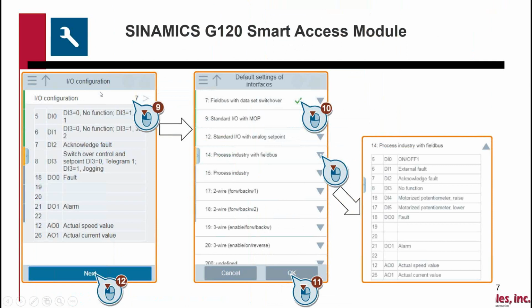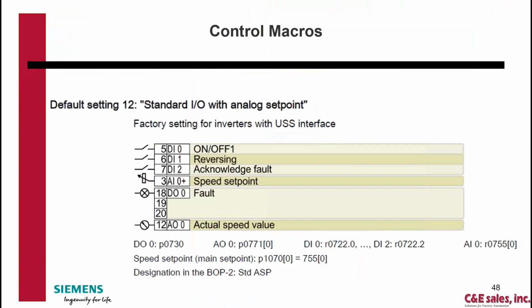So next, you're going to have IO configuration. We've got some examples of what we're going to do. Here's the different options we have from 7, which is field bus. For our example, we're going to do 12, which again is standard IO with analog. If you click the arrows, it's going to show you what that's going to look like, what parameters the digital inputs and such are set to. Again, we're selecting 12, so that's going to be standard IO with analog set point.